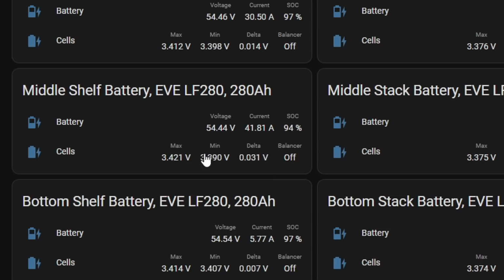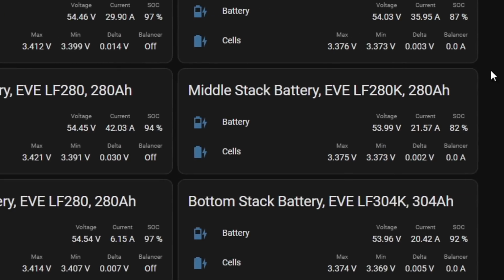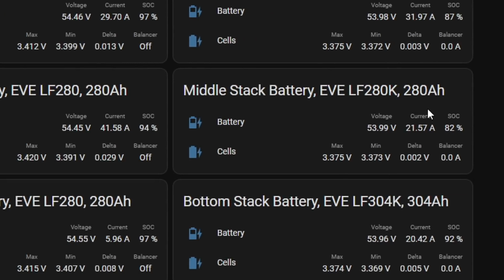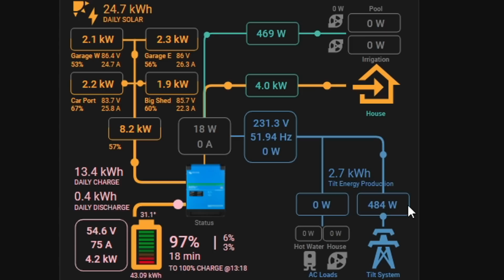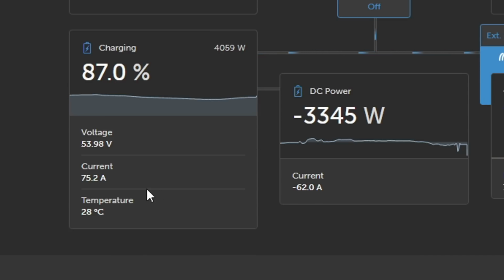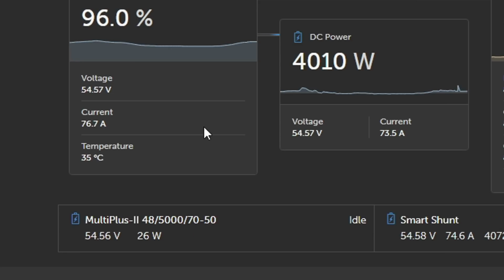Perfect. Yeah, and the aluminium bus bar battery is now catching up. Top one is lower. Bottom one is already saturated at this voltage here, but the middle shelf battery with aluminium bus bars is now catching up because it charged slower all the time before that. And you can also see the Gobel tower is now catching up as well. The top battery 31 amps, 21, 20 amps. See, it has actually increased the frequency now to 52 Hertz to limit the tilt system, because I set the charge current limit to 150 amps. We don't want to have more than 150 amps in the system. So what I'm seeing here, 75 amps going into the Gobel tower and around 76 amps going into the battery shelf. So it's almost 1-to-1 now. Let's see how they're balancing out.